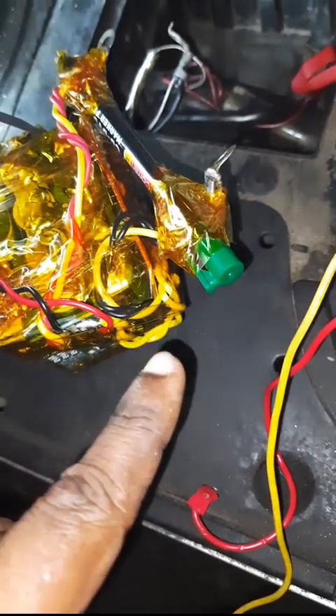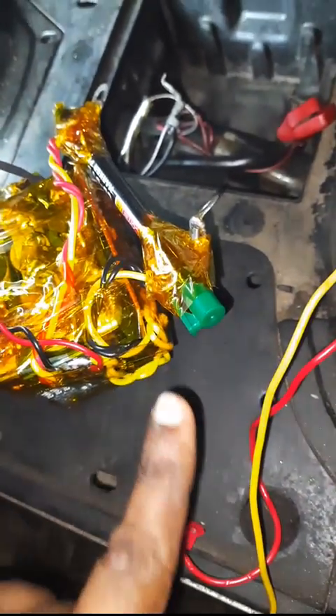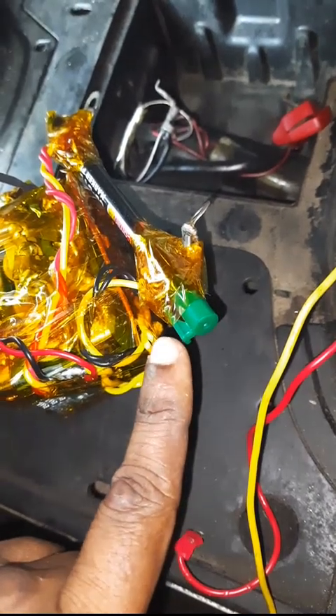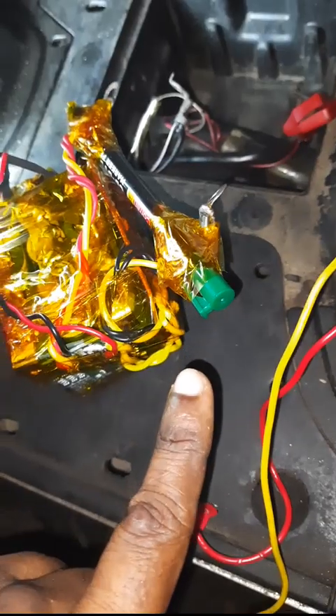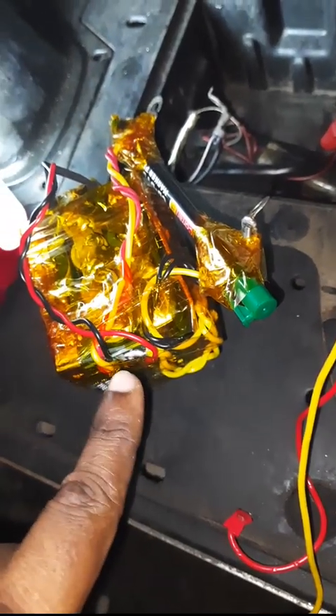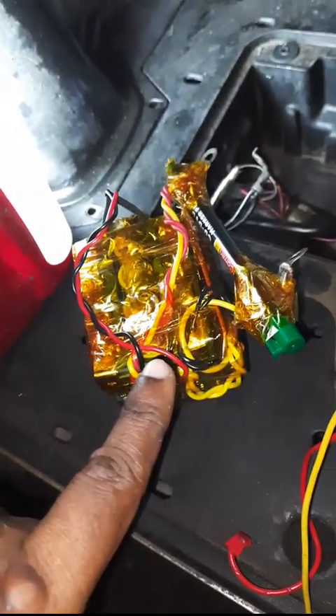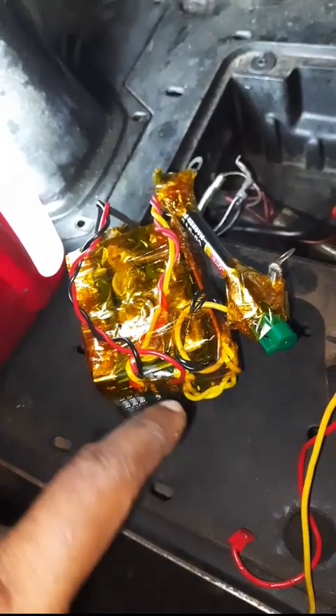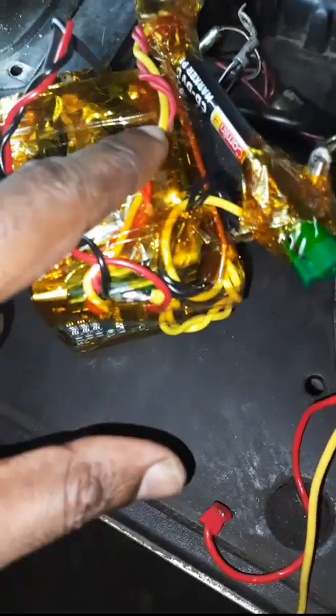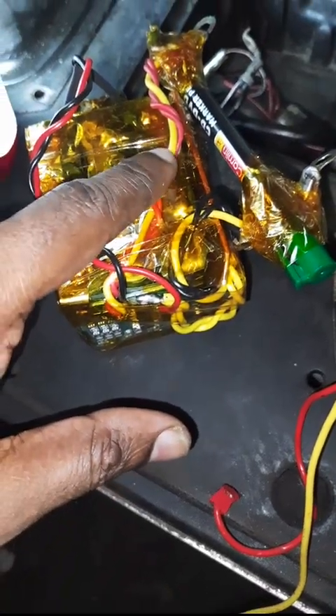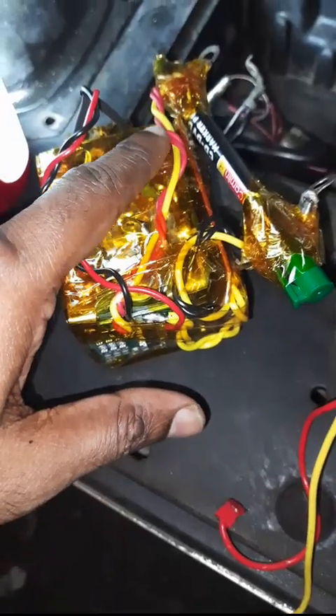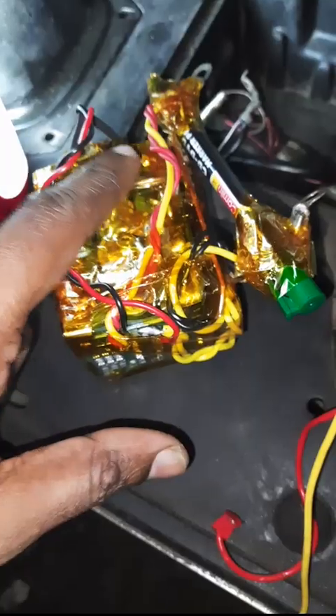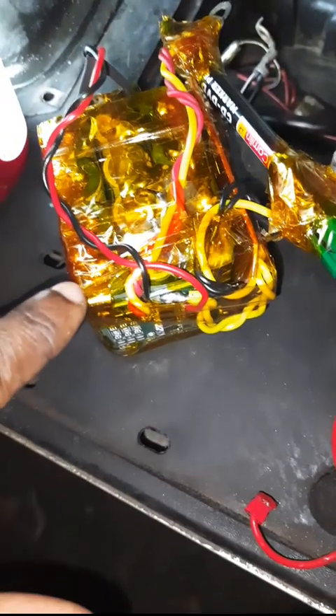So you have to be careful. You cannot put a lot of thick wires in this small board, but the wires have to be sufficient, otherwise this 70-80 amps cannot be drawn. So this much thickness, 1 square mm wire has to be there minimum. I have put 2 extra 0.75 thickness wires also.